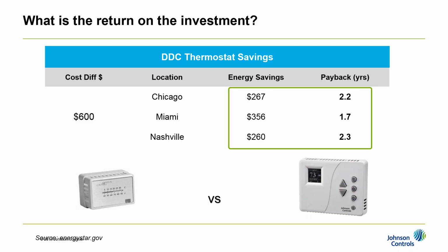Someone heard that the scheduling is 5 and 2 days for a setback. Is there going to be a 7-day scheduling thermostat, and can that be done through the BAS? Yes, the BAS is the overall governing system, so you just implement your schedule as needed right into the BACnet points to achieve that. We weren't planning on changing the standalone mode from 5-2. Really, if you wanted a 7-day schedule, you just make the weekend settings the exact same as the weekday settings.